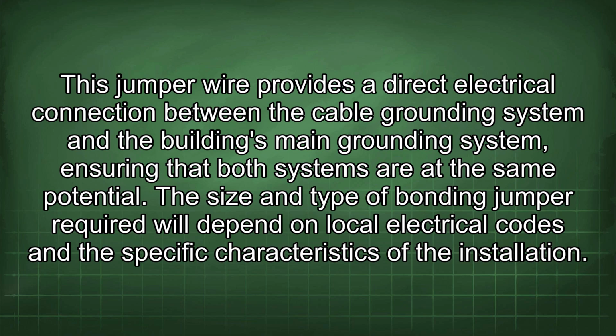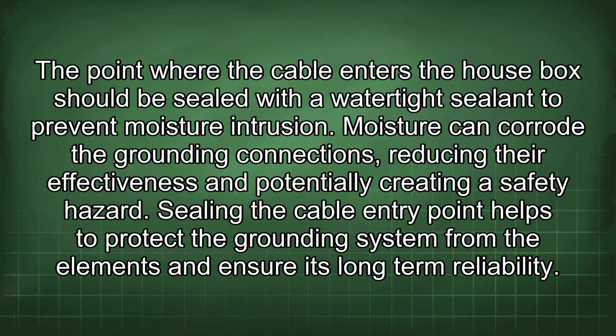The size and type of bonding jumper required will depend on local electrical codes and the specific characteristics of the installation. The point where the cable enters the house box should be sealed with a watertight sealant to prevent moisture intrusion. Moisture can corrode the grounding connections, reducing their effectiveness and potentially creating a safety hazard. Sealing the cable entry point helps to protect the grounding system from the elements and ensure its long-term reliability.